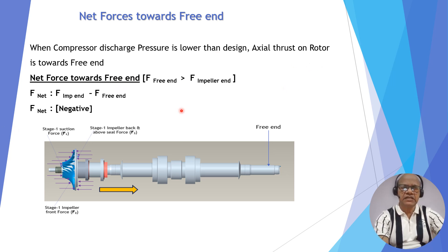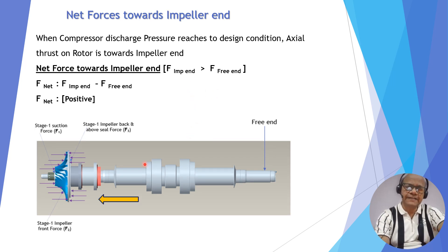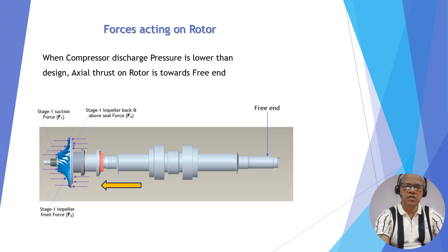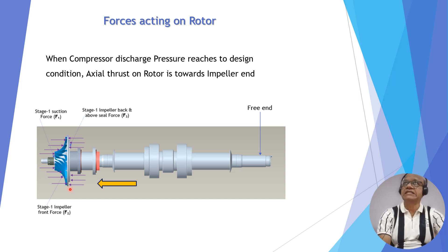When the machine is operating at lower discharge pressure, the back-wheel pressure is lower, so F3 is less than F1 plus F2, and the rotor is thrusted toward the free end — as shown in the diagram. When the compressor reaches design condition, the back-wheel pressure force becomes greater than the combined front and suction forces, the net force becomes positive, and the rotor is thrusted toward the impeller end. Therefore, at design condition for a single-stage machine, the rotor is always thrusted toward the impeller end.